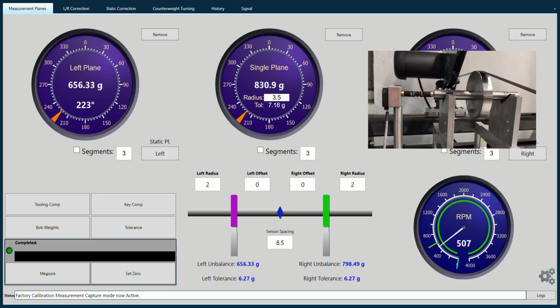The sensor mapping process involves taking a series of readings so the software can identify the phase shift of your machine and sensors. It is recommended to start with a reading at 300 RPM and then take readings every 50 RPM up to around 800. If the arbor starts to bounce or rattle at any point before reaching 800 RPM, don't take any more readings as this can affect the mapping.